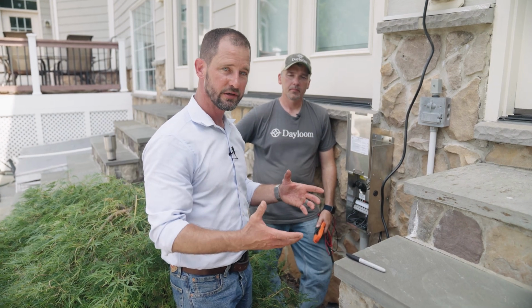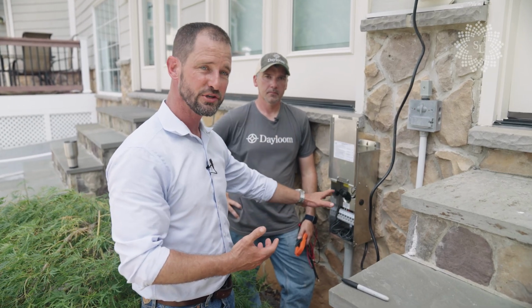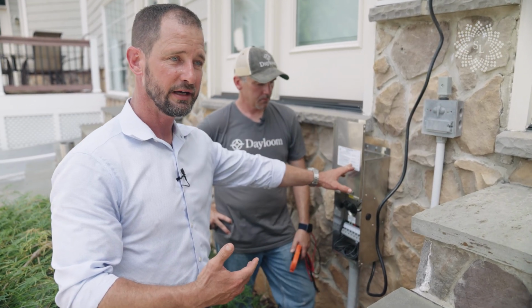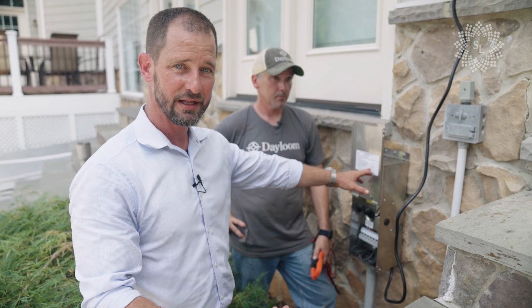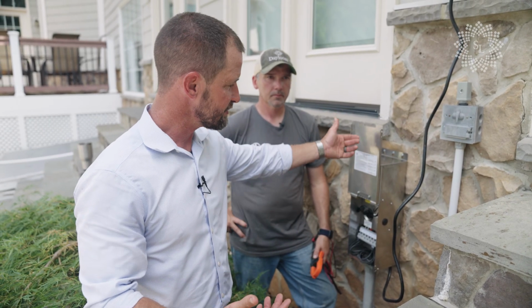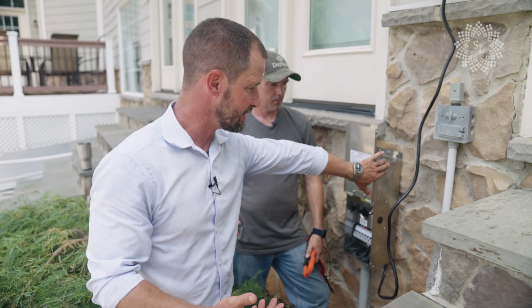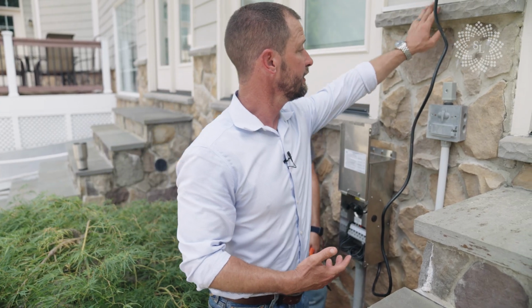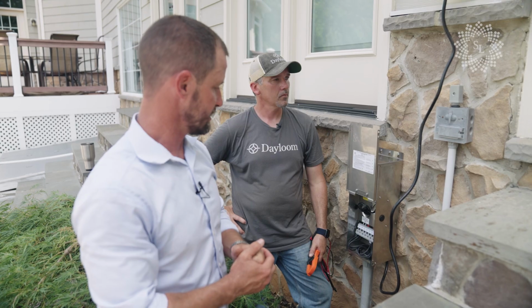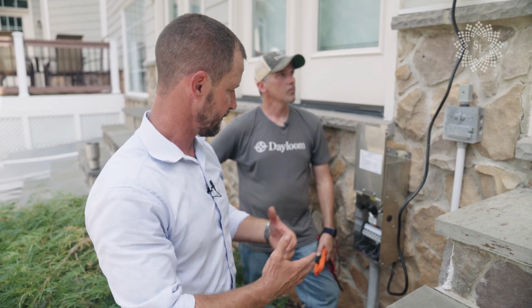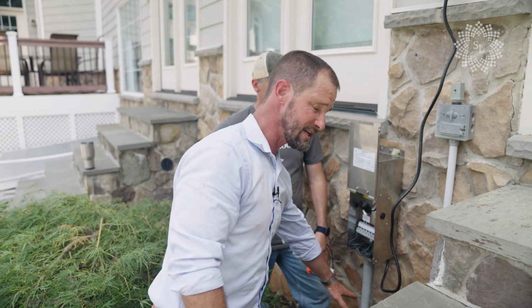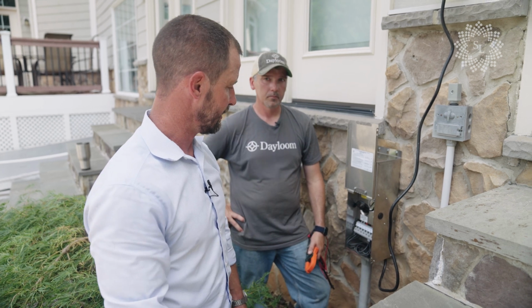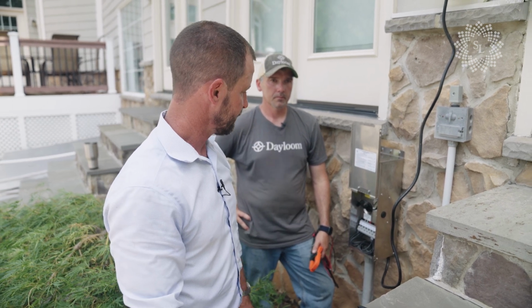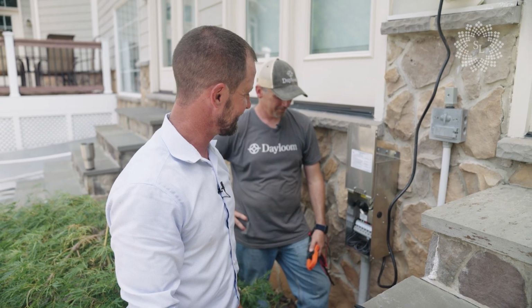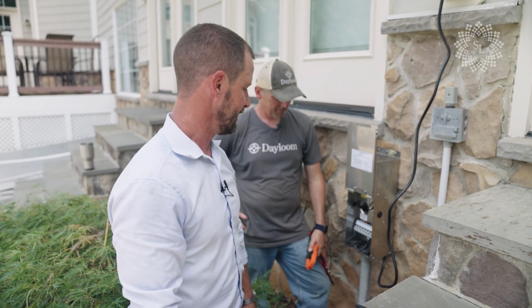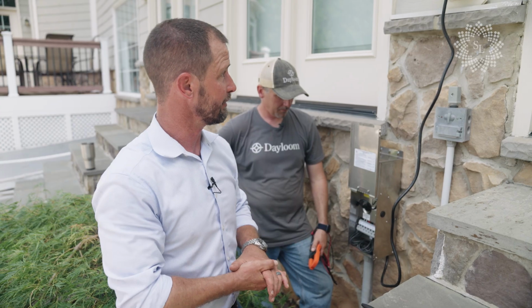So the last thing we're going to do is go through final inspection. We'll write everything down, put everything in our notes. We'll also take photos of everything on the project, and do the full cleanup. This transformer is typically a little higher than we had, but there are already drill holes in here, and we also had the outlet that the customer chose to stick with. So it's a little higher than we typically like it. It does have to be over 12 inches off the ground, but it doesn't have to be 3 feet off the ground. It's easier for technicians to get to it, and so Josh and I go back and forth on that. But typically I'd like to put it down lower in a spot a little further away.